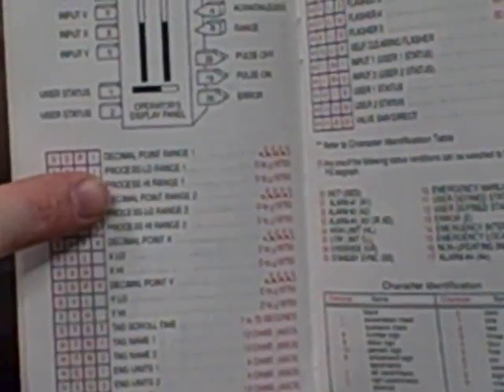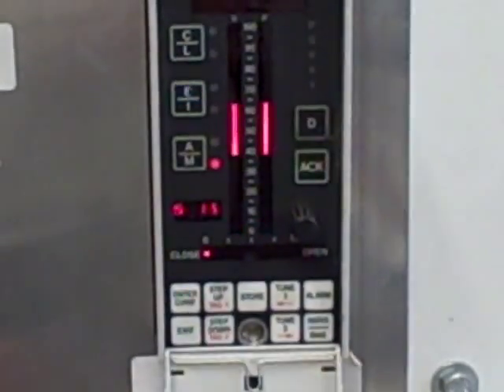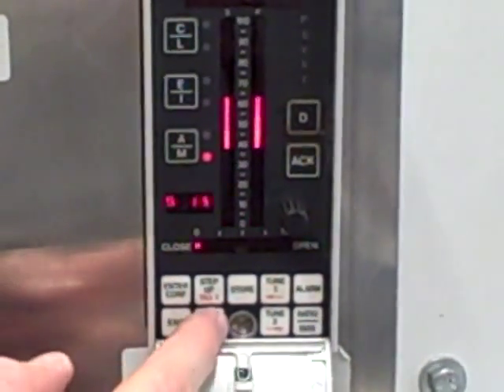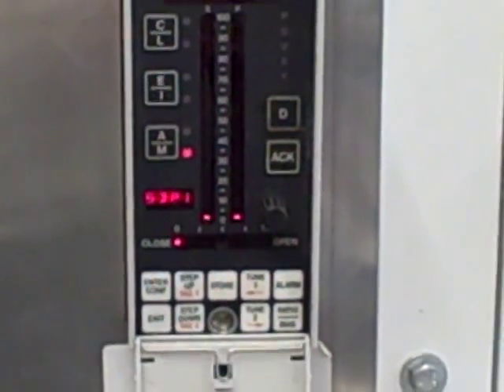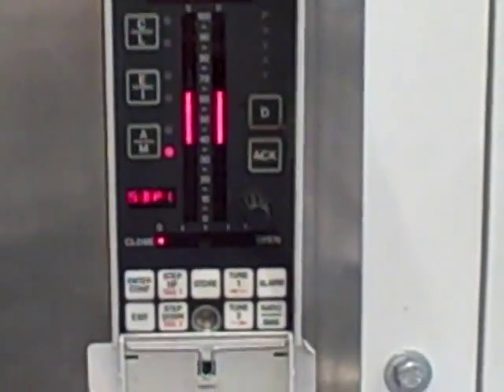So remember I wanted to get to function block 15, which is where my process high and low range points are. So I spin that until it says S15, and once again I step down into the menu. SDP1, process point range 1. That's actually decimal point. If I step down again, you see the decimal point position which I can change using the knob.